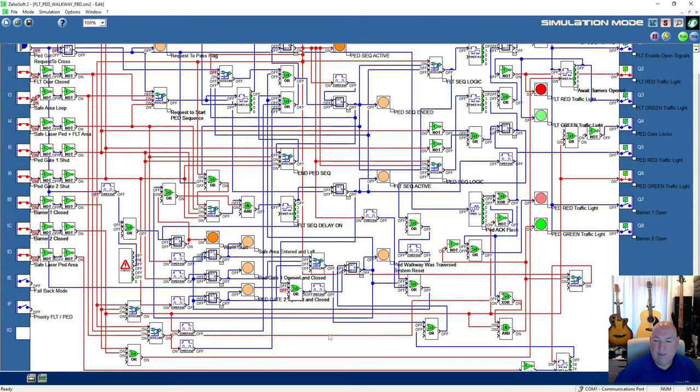Let's just leave it and see what happens. Let it run through, see if it cancels back to FLT mode. I'm not going to go through, I'm not going to do anything. So it should cancel back. So it'll override if nobody goes through. But we want it to cancel the override, cancel the timeout, if they've started to go through the system. Let's see what happens. Right, so it's cancelled it, it's switching back to FLT mode.